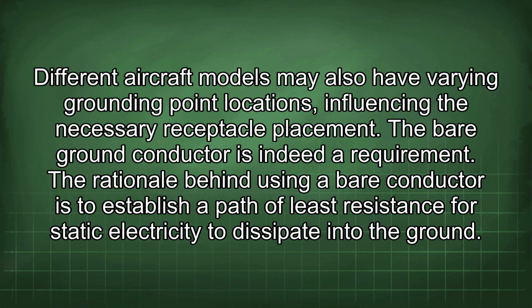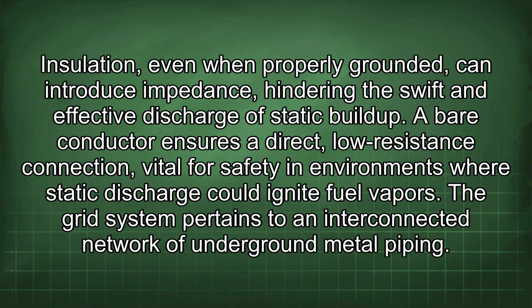The bare ground conductor is indeed a requirement. The rationale behind using a bare conductor is to establish a path of least resistance for static electricity to dissipate into the ground. Insulation, even when properly grounded, can introduce impedance hindering the swift and effective discharge of static buildup. A bare conductor ensures a direct, low-resistance connection, vital for safety in environments where static discharge could ignite fuel vapors.